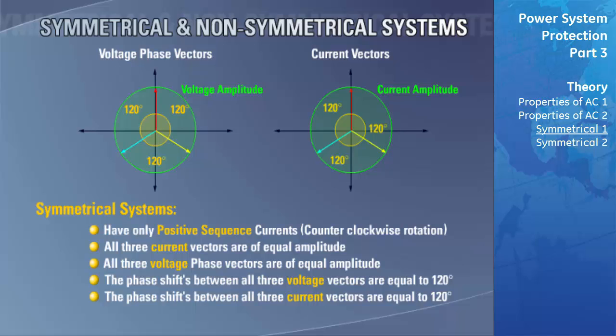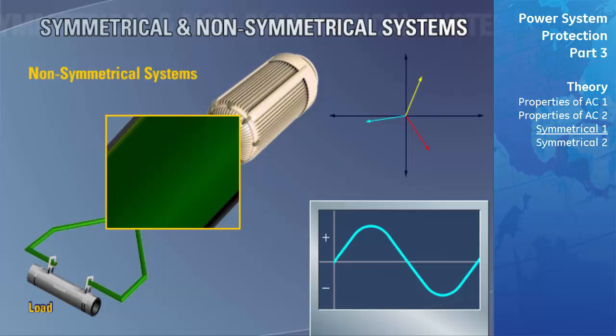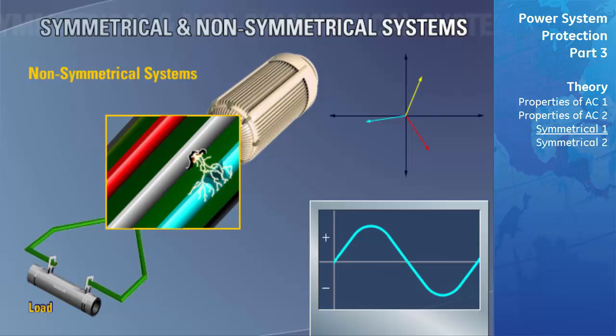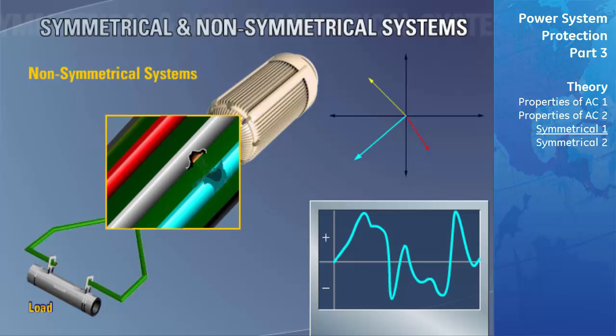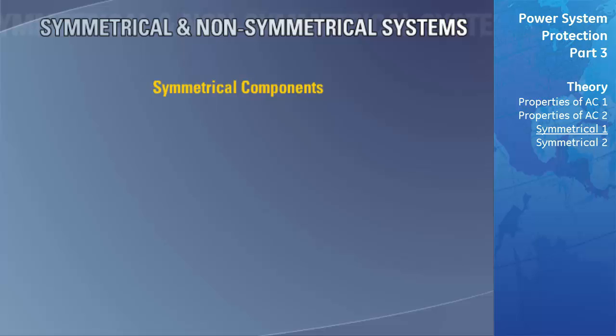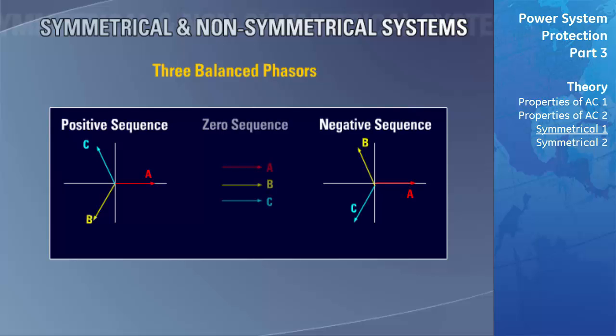If one or more of these conditions is not met, the system is said to be non-symmetrical or unbalanced. Under normal operating conditions, an electrical power system is considered symmetrical from the generator to the load. When a fault or unbalanced condition occurs — such as a phase-to-ground or open conductor fault — the system is said to be unbalanced. Symmetrical components is a methodology developed in 1918 by Charles L. Fortescue, allowing the line-to-neutral or line-to-ground voltage and current phasors of a non-symmetrical system to be calculated.